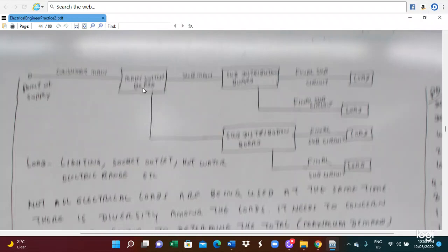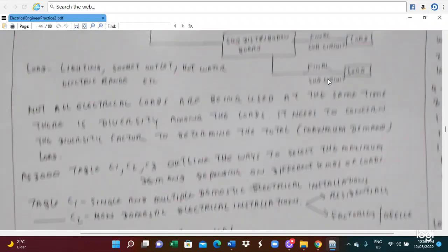From the main switch, there will be the final sub distribution. The wire between the main switch and the sub distribution is what we call the sub main. Then from the sub main, we connect to the final load. The load is what we call the final sub circuit. The load can be a lighting load, a power load, a socket outlet load, a hot water load, or an electric water heater. So they are different kinds of load.